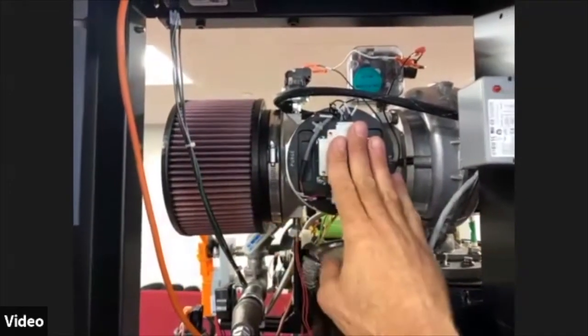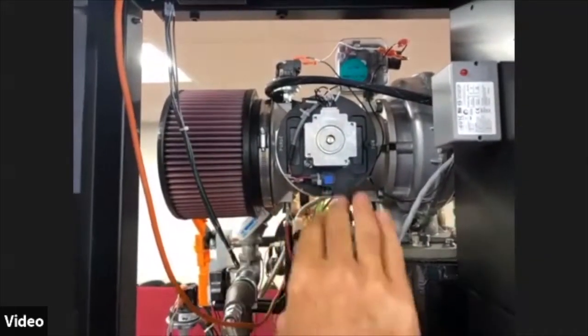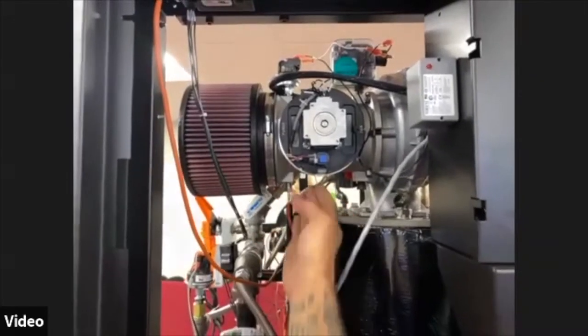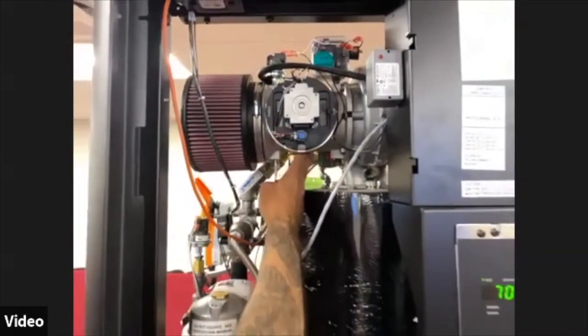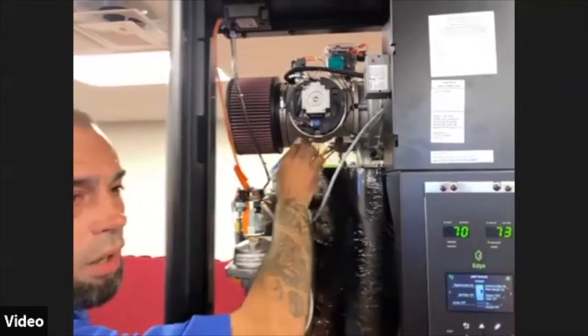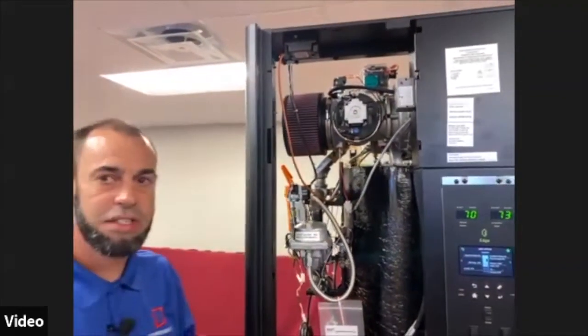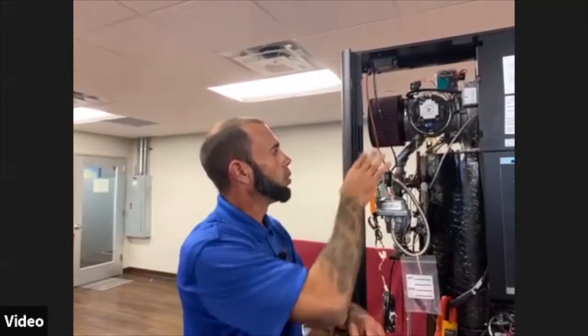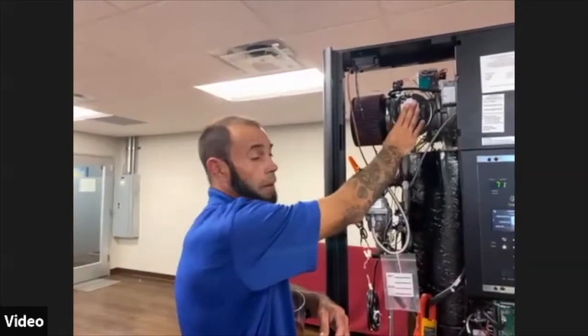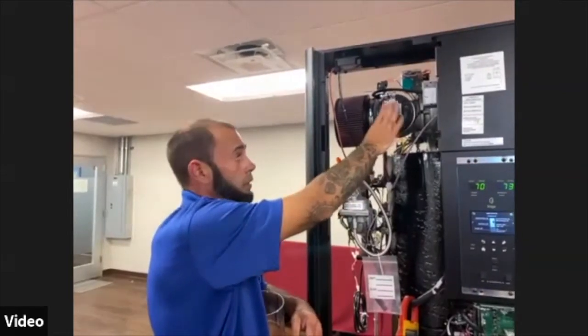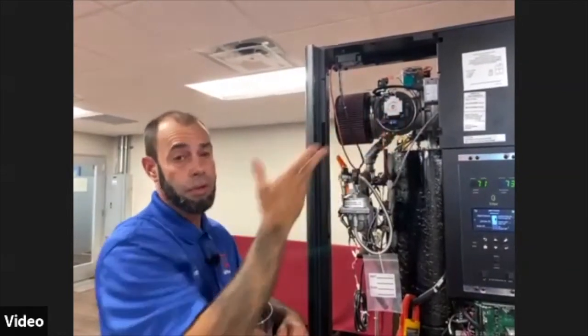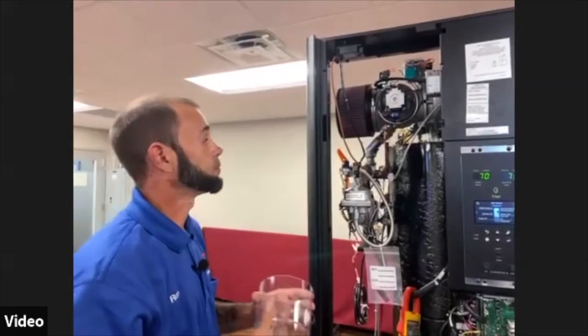This is our stepper motor, which actually rotates our air fuel valve. Internally inside of the air fuel valve as well, we have a butterfly. We also have a Teflon sealing ring, and we also have a gas shutter and a gas plate in there as well. Important to note that this is not a repairable component. If there's anything wrong with this air fuel valve, you'll have to replace the whole assembly.